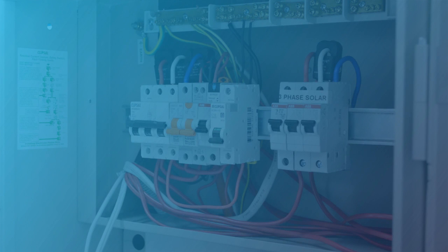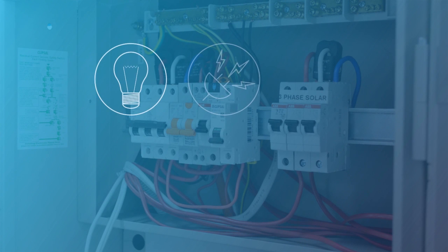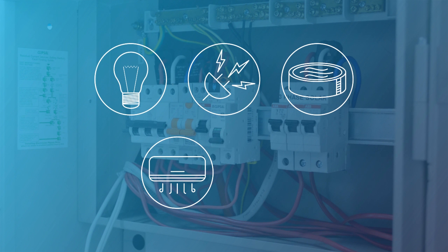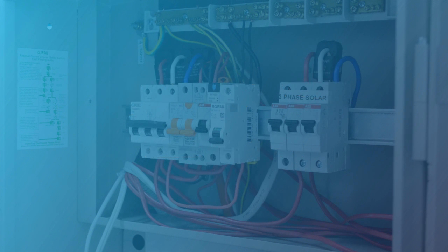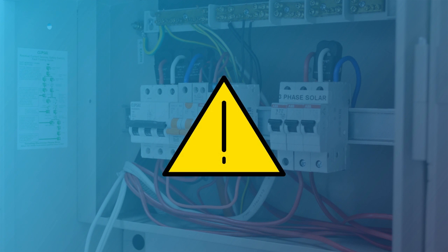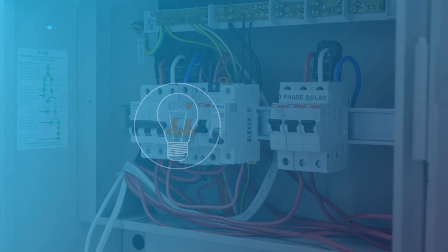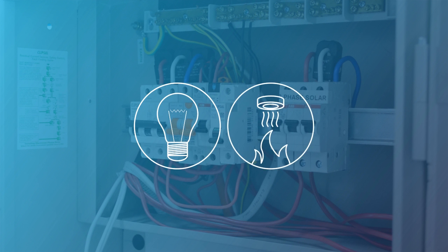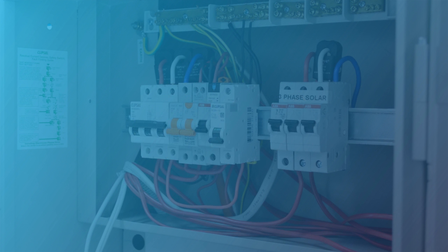Examples of circuits that can be switched are lighting, power, pool pumps, air conditioners if suitably rated, and electric hot water systems. It is important to check before switching lighting if there are any hardwired smoke detectors on the lighting circuit to be switched. If there are hardwired smoke detectors, it is important not to switch lighting, as this will also switch off the hardwired smoke detectors.